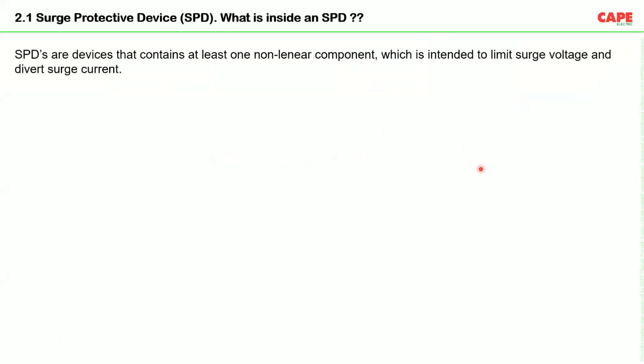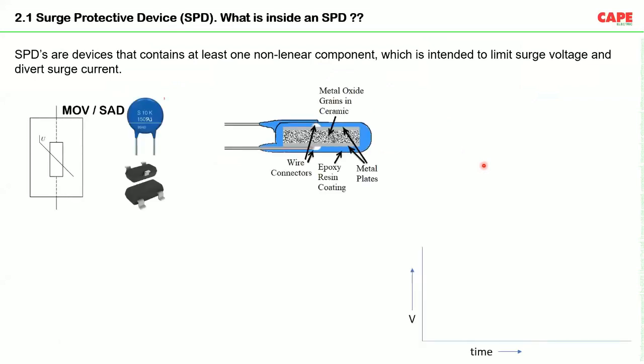And what are the components? What is inside an SPD? An SPD contains at least one nonlinear component which is intended to limit surge voltage and divert surge current. For example, it sometimes has MOVs or silicon avalanche diodes. In the MOV's internal construction you can see metal oxide grains in ceramic. Anyway, our idea is not to educate on what an MOV is, but to find out how it works.